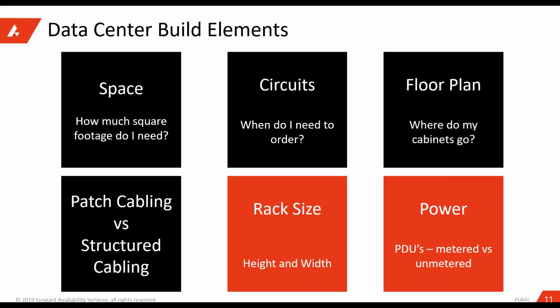Structured cabling, on the other hand, usually terminates on a patch panel. Terminating on a patch panel means the cabling—I won't say it cannot be removed, but normally it's stationary. It goes back to another patch panel, and your core plugs into that. It does take up rack space, so you need to be aware of it, but it also minimizes your patch cabling. By minimize, I mean you don't have 20-foot runs for patch cabling—you may have 5 to 7-foot runs from top to bottom of the cabinet, plus another run back to the network core.